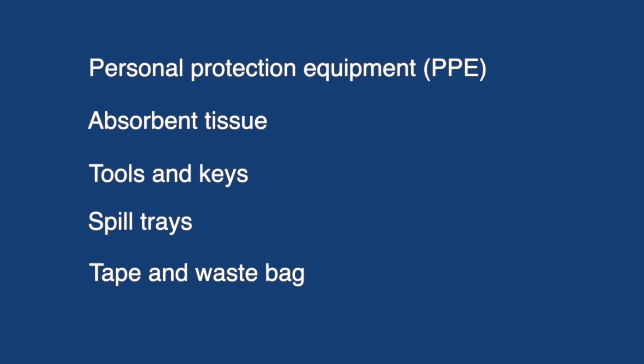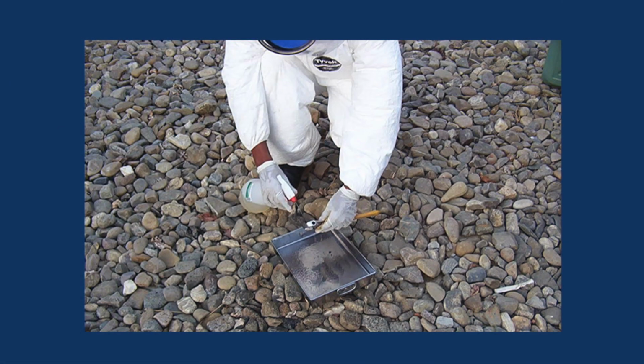It is recommended that the facilities have an oil spill containment kit of a larger capacity, as spills may occur when loosening the valve or due to a deteriorated welding. All sampling material, such as trays and tools, must be cleaned with organic solvents to be used again.